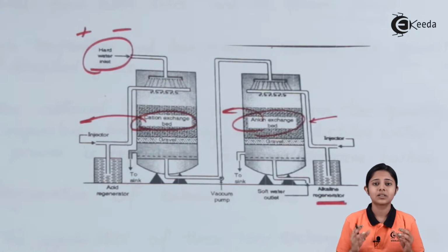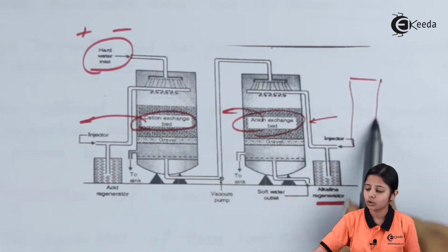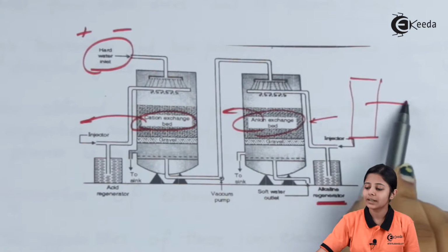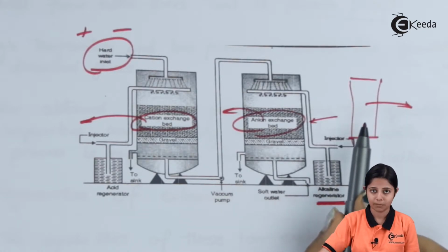That means there can be a certain amount of dissolved gases, such as dissolved oxygen or dissolved carbon dioxide, which lead to contamination of water and eventually to the hardness of water. And thus we should have a degasifier. Now a degasifier is nothing but a sort of container. Over here all the gases are removed, and this degasifier also has vacuum pumps in it.